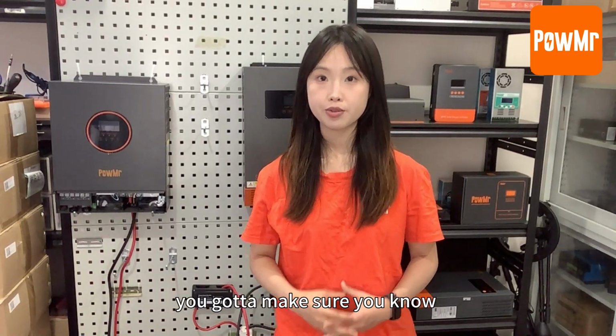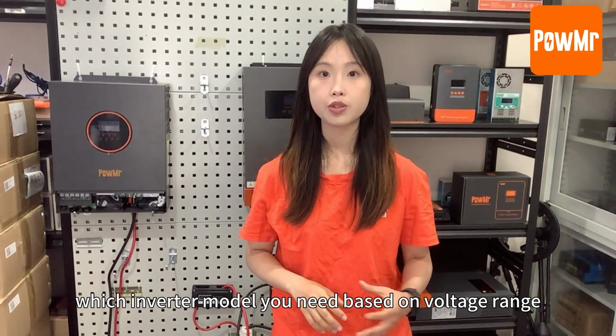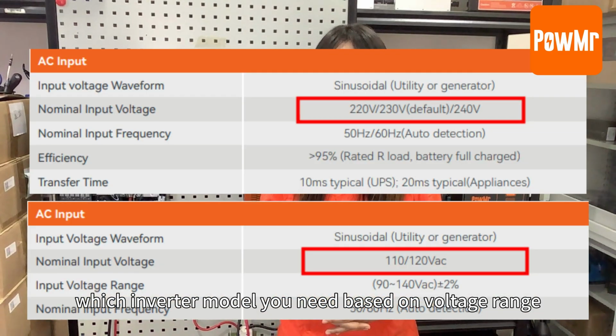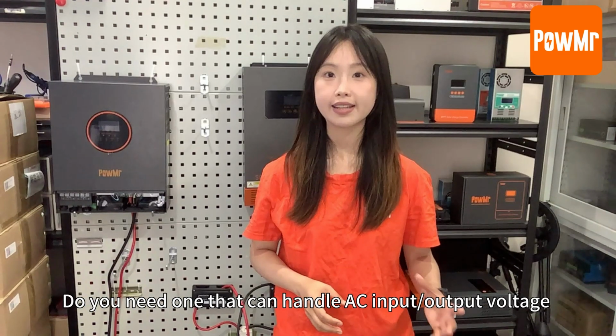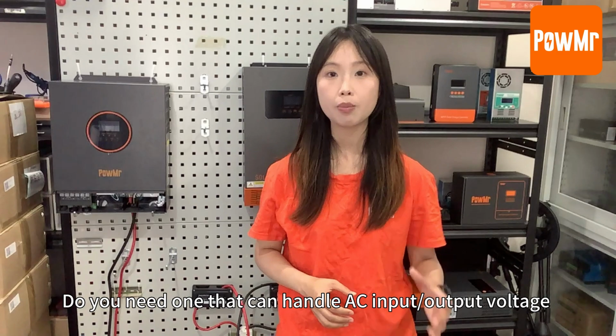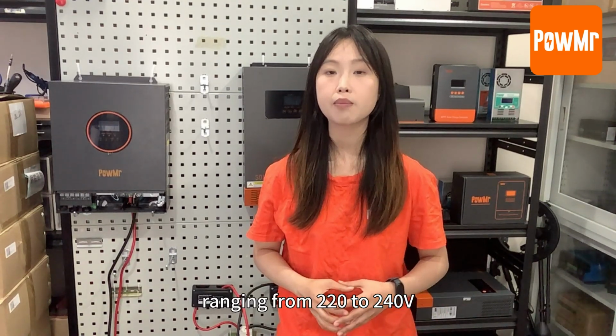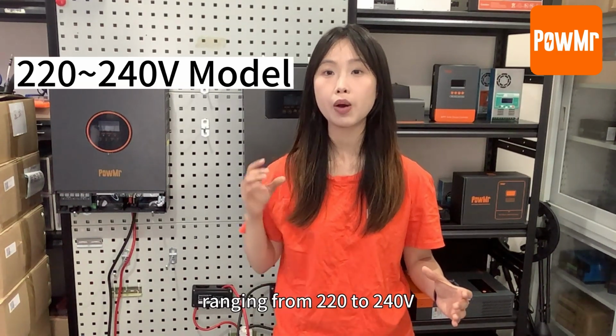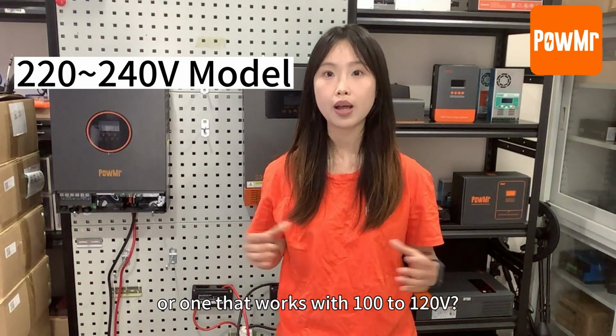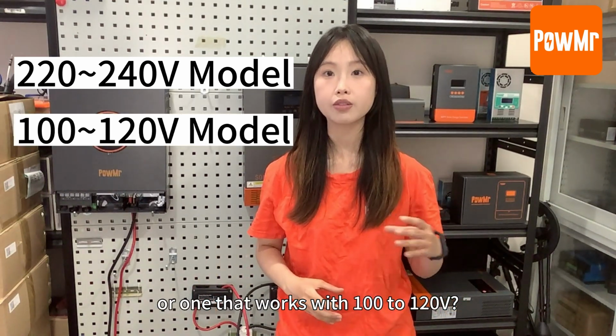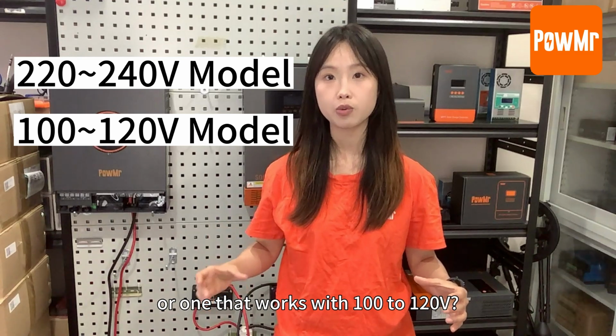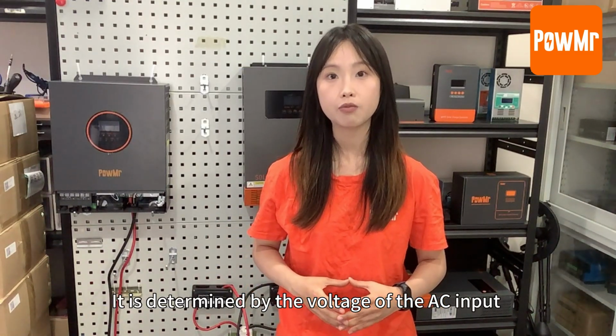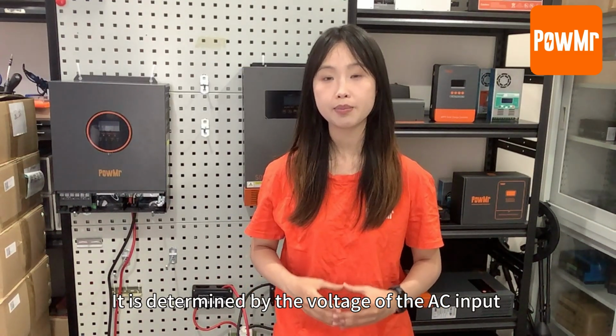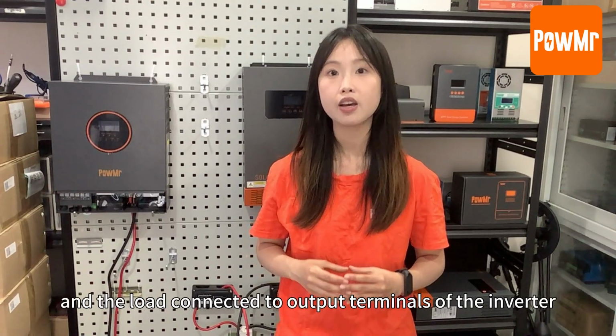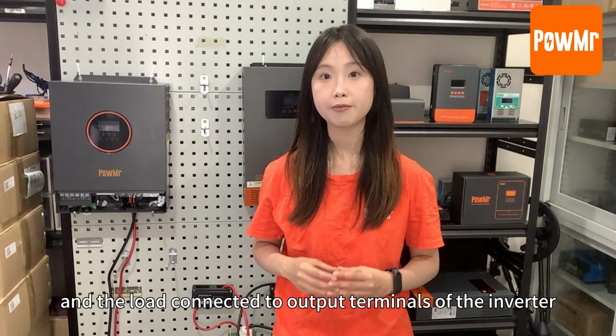First, you gotta make sure you know which inverter models you need based on voltage range. Do you need one that can handle AC input or output voltage ranging from 220 to 240 volts, or one that can work with 100 to 120 volts? It is determined by the voltage of the AC input and the load connected to the output terminal of the inverter.